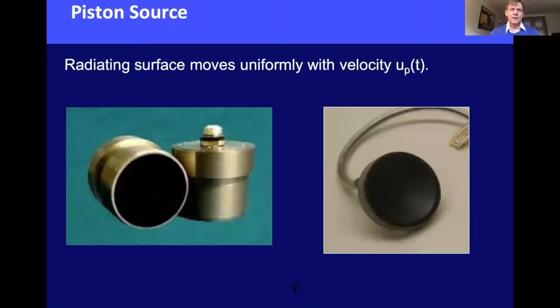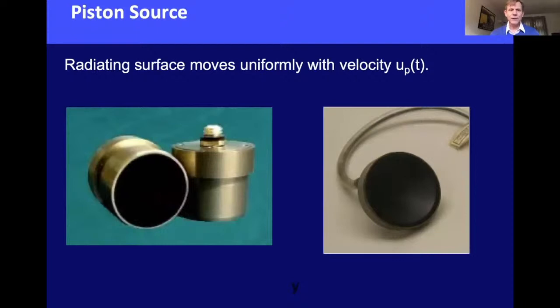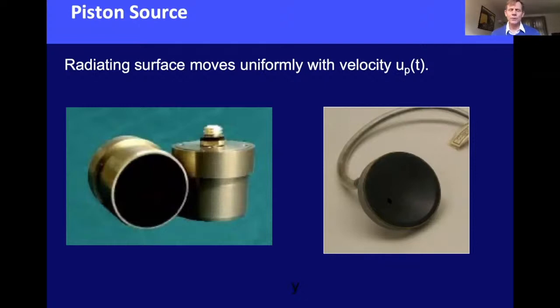Now we move on to acoustic sources and diffraction. Most acoustic sources used for ultrasound are piezoelectric. A flat unfocused transducer is a piezoelectric disc — apply a voltage across it, it changes thickness, and as you oscillate the voltage the thickness oscillates, giving a velocity source. A curved piezoelectric transducer has been shaped so it creates a natural focus at the radius of curvature. These are the two most common sources in biomedical ultrasound.